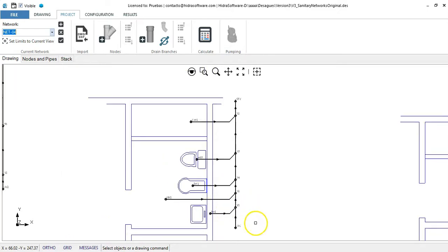The best thing we can do in this case is to propose a branch vent that runs along the line defined by this wall and reaches this point. Here, this branch vent will be connected to the vent stack that, in turn, will be connected to the soil stack. Finally, individual vent pipes required from the fixture's drain pipes will be connected to this branch vent. We are going to sketch it out manually in the isometric view.